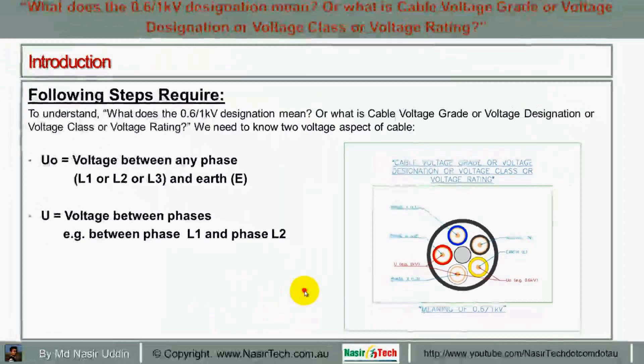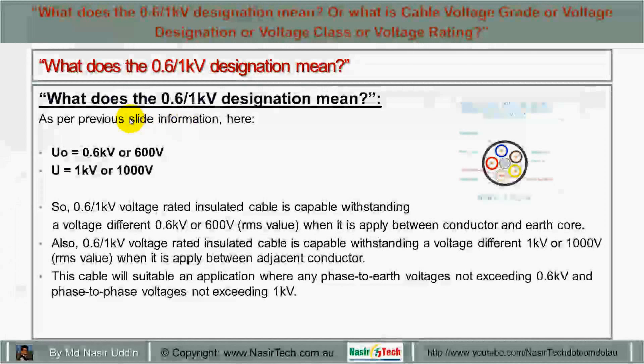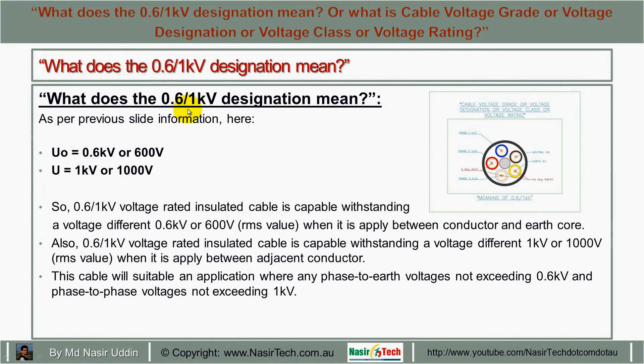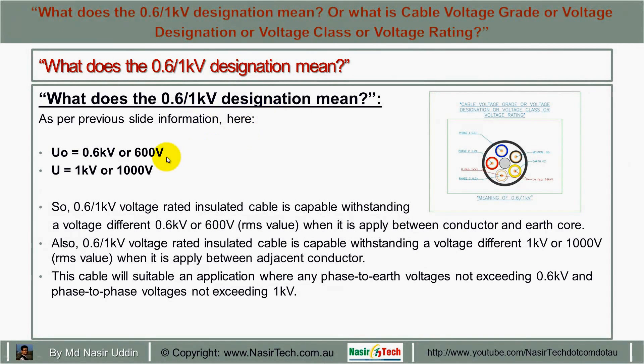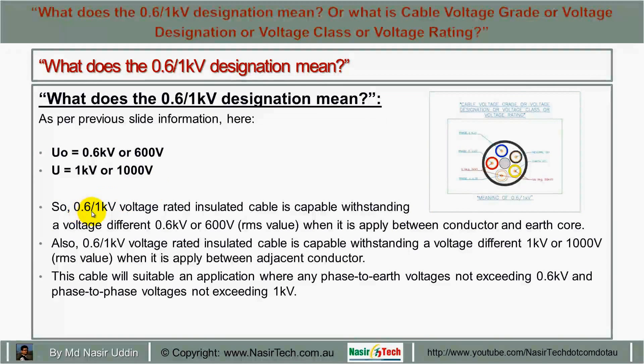With the above information, when we mention the 0.6/1 kV designation, this means U0 equals 0.6 kilovolt or 600 volt, and U means 1 kilovolt or 1000 volt.